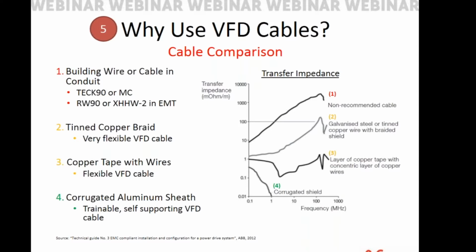It actually becomes a much better conductor than copper, the aluminum itself. So this is where many engineers get kind of muddled up in saying, well, copper is a better conductor than aluminum. Well, not really. It depends on the frequency we're talking about. In building wire frequencies, absolutely. When it comes to a VFD, aluminum is preferred.